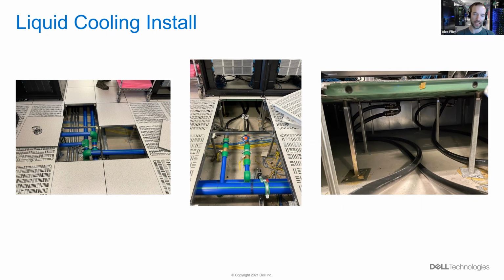On day one, we only had about 1.5 racks ready to go, so we hooked those up. Over the next couple of weeks and months, as we added systems and converted things, we were able to plug them in and keep going. We did not have to shut down the system to do this - you just hook up the quick disconnect, turn on the valve, make a couple of checks, and you're off to the races. We really like the flexibility of this system, and we're definitely going to be seeing more liquid cooling as time goes on.